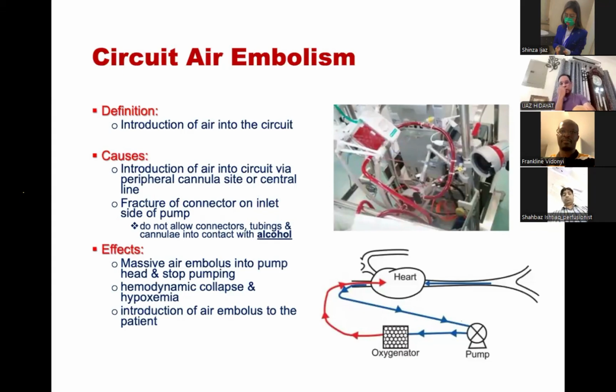Okay. So usually what we experience is that air can enter the system when you need to add another cannula on the venous side. Like you want to increase the flow and the drainage, so you add a second cannula, and there is a chance you can suck in air. Then some of the centers are doing hemodialysis through CRT, through the circuit, and not even through the circuit, even through the lines available in the neck or wherever they are using, and they forget, once they finish the CRT, to stop the three-way, and air can enter the system that way. So that can be a cause, and sometimes the cannula dislodges, or there are leakages in your connectors, which can create air entering into the system.